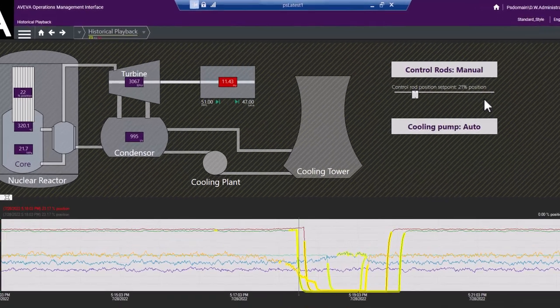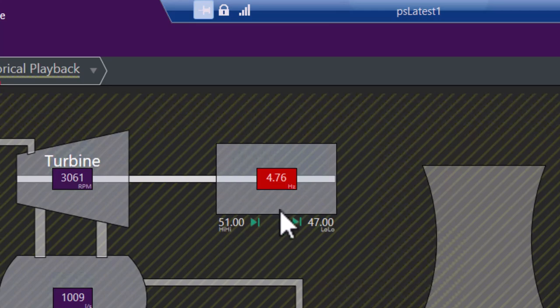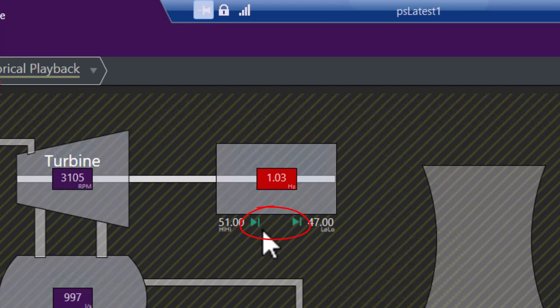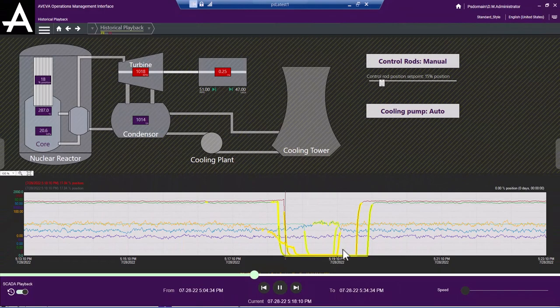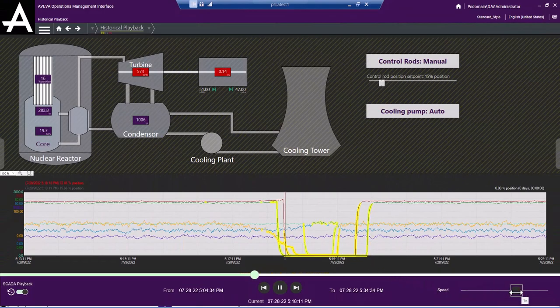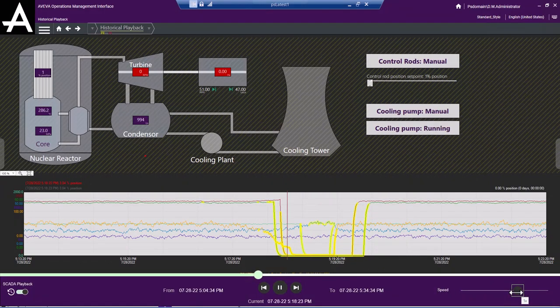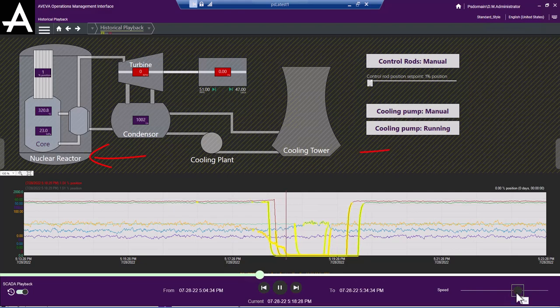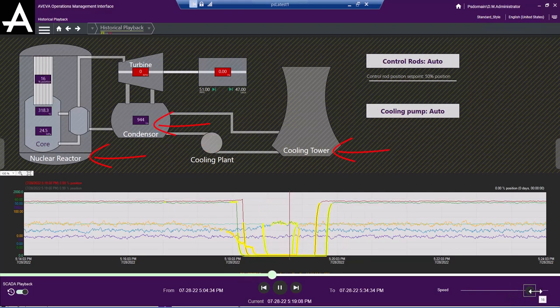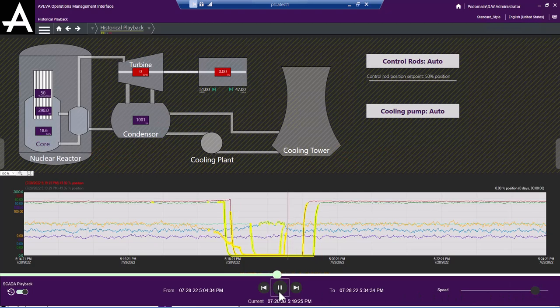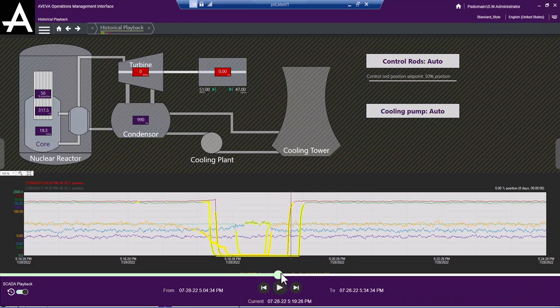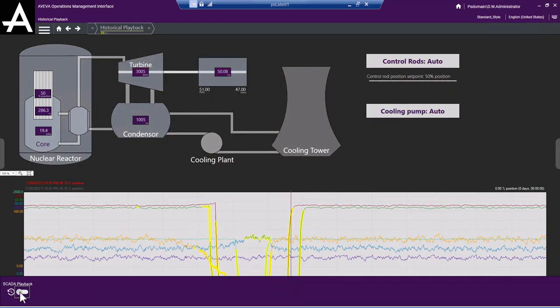This can lead to some confusion for things like alarm limits, etc., that may have been historized, or may not have been historized. And to indicate that we are showing a live value during historical playback, we've got a little indicator there that's a status icon. You can modify the status icon to display something else if you wanted to, or you can just leave it off. So I've left it off for all the tag names, descriptions, engineering units here. But for the alarm limits, I'm just putting those tags on there, just to make the user aware that he's looking at values that are not historized. He's looking at historical data, but these alarm limits are not historized.